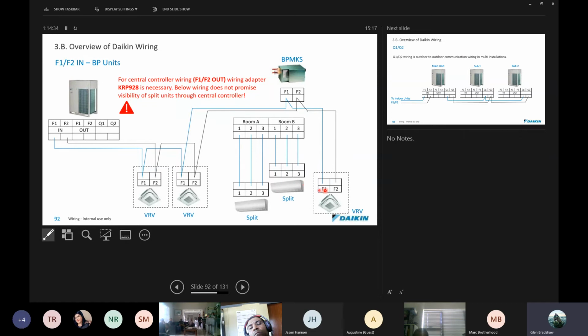BP boxes, okay, these are expansion valve kits. They're not a BS box, they're a BP box. They're basically an expansion valve that allows us to use RA equipment. These are split type units that would normally have their own condenser. Some of them are compatible with VRV, but they have to be connected through an expansion valve kit.